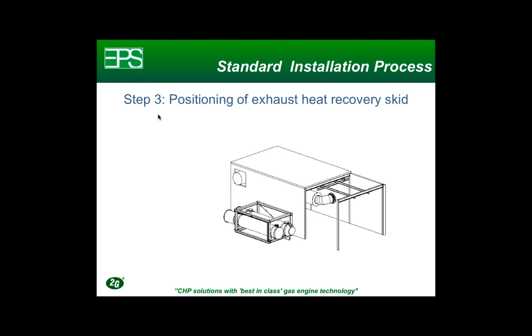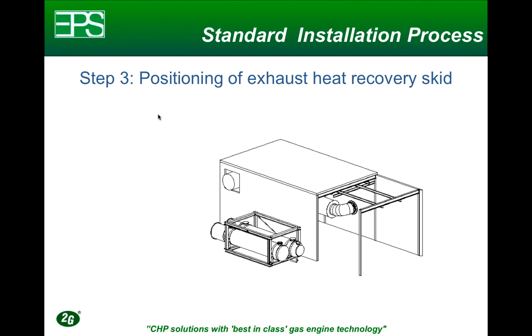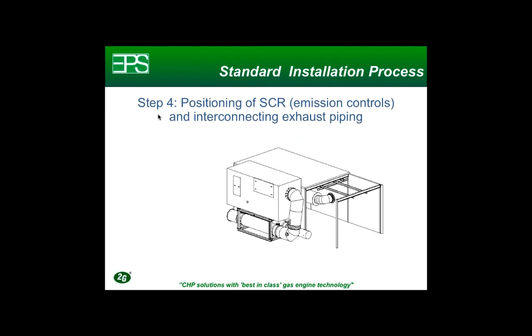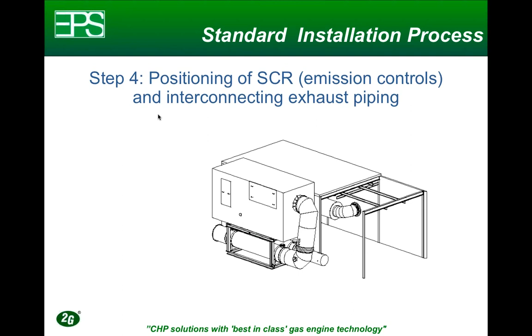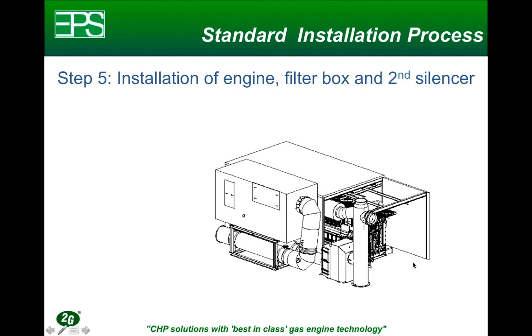Then we position the exhaust heat recovery equipment. On top of the exhaust heat recovery equipment is the SCR system, the exhaust cleaning equipment. Once that's done, the filter box and the second silencer are installed. And I forgot to mention, the engine is also moved into the enclosure. So at this point, the engine is in place and most of the key components are installed.